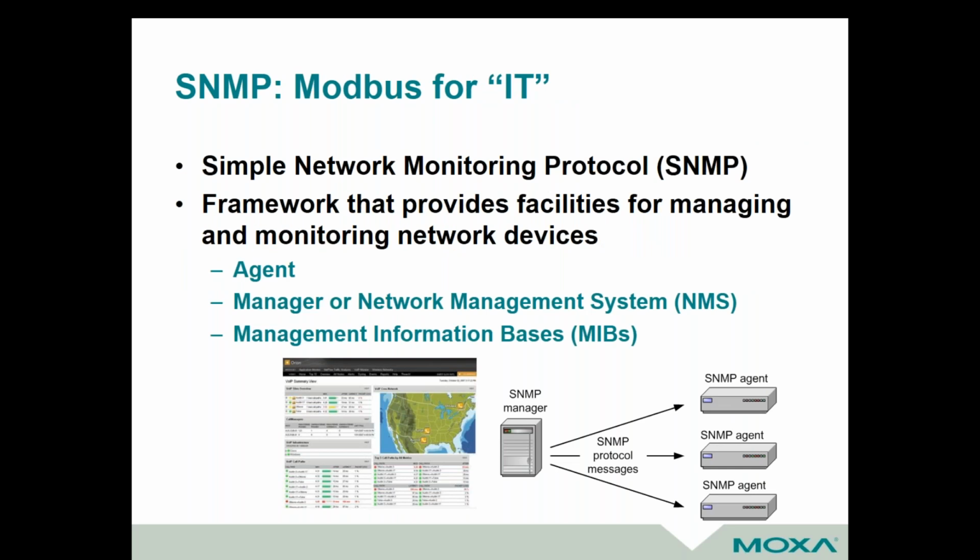I was pretty fortunate. I spent almost 10 years on the IT side of things, working in data centers, and learned a lot about what these guys do to maintain these massive server farms. There's some really interesting technology. This one's a little old, but still pretty useful. I've always referred to it as the Modbus of IT. It's called SNMP, Simple Network Management Protocol, and basically it's a client-server, master-slave type system that has software running on a central PC, and that PC is able to poll those devices and get status.